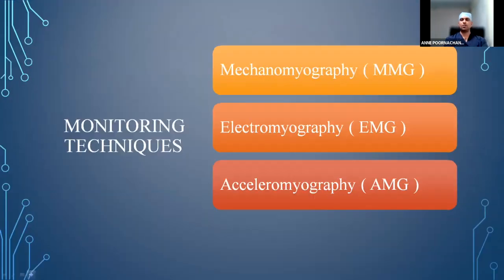The monitoring techniques include mechanomyography, electromyography, and acceleromyography. There are some other techniques, but they are not used clinically or not widely available. Mechanomyography is the gold standard, but clinically not used because of the bulky apparatus, and it is not possible to set up in the OT. It is not feasible.